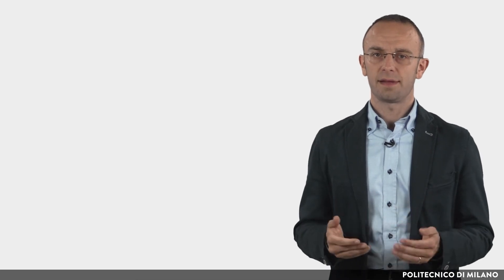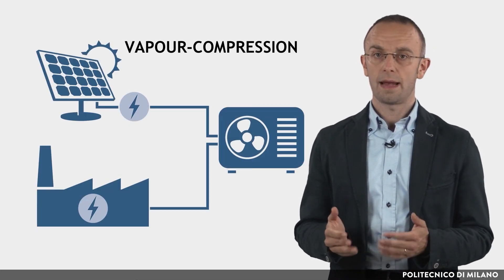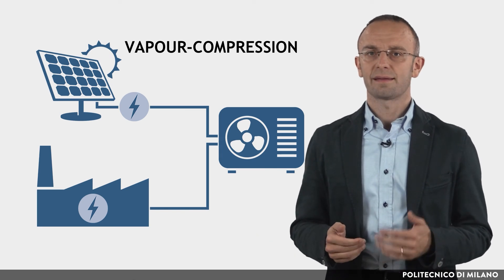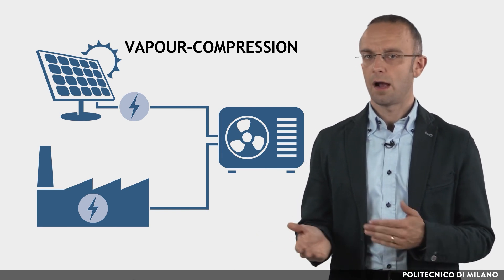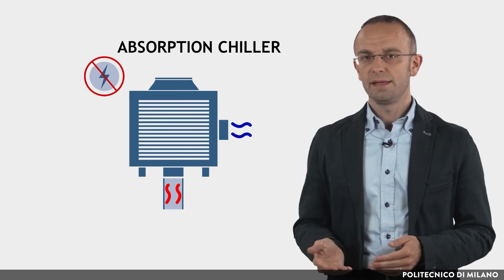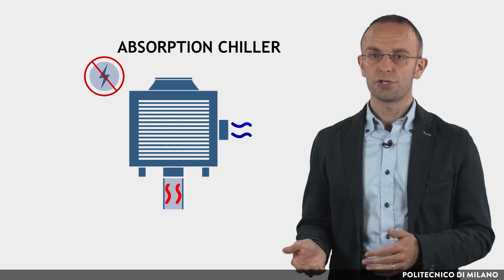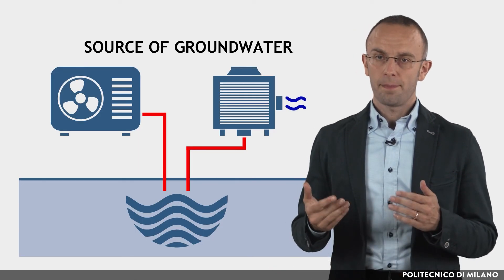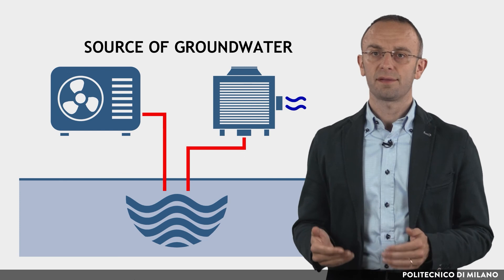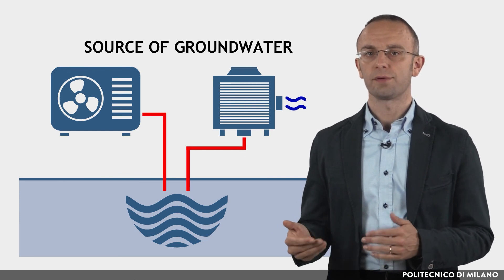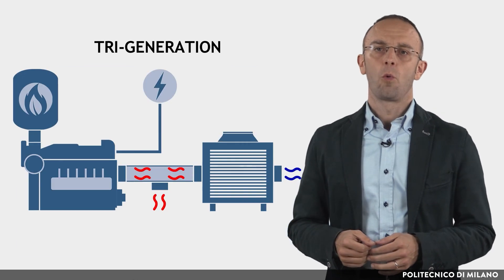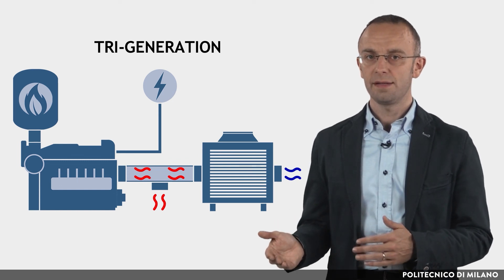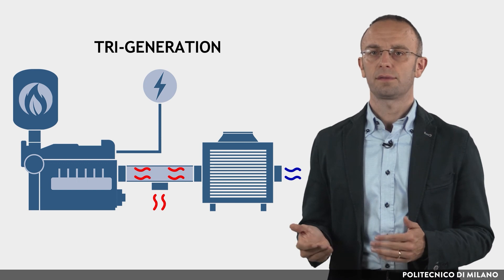In conclusion, if electricity from the grid is available, or renewable electricity can be easily generated on-site — for example from photovoltaics — electric heat pumps are a very good option for heating and cooling. In the presence of waste heat or low-cost heat sources, absorption chillers can be successfully used, especially if electricity is scarcely available. For both vapor compression and absorption heat pumps, the presence of groundwater sources allows increased system efficiency. Where there is a constant need for thermal energy and grid electricity is not always guaranteed, tri-generation represents an interesting technical solution.